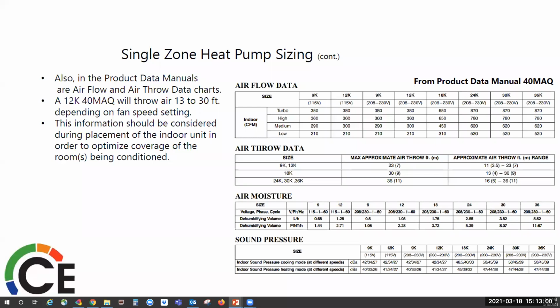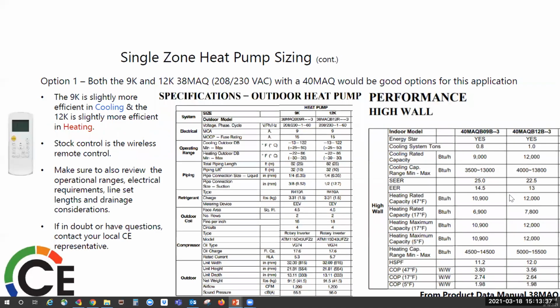Another consideration is air throw, especially on the high wall systems. It depends on how long your room is. If it's wide, you want to consider how far the air can go down there. You don't want all the air at one end. You want a good balance. See right here on the 9,000 and 12,000 BTU units, it'll throw approximately 23 feet. You want to refer to your product data manual to know this.